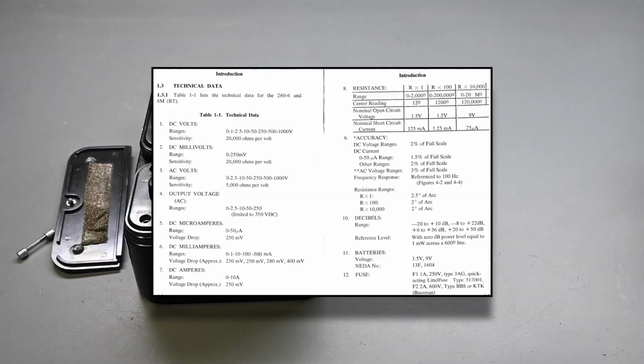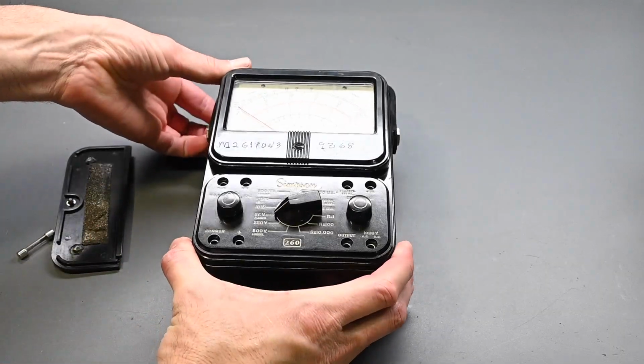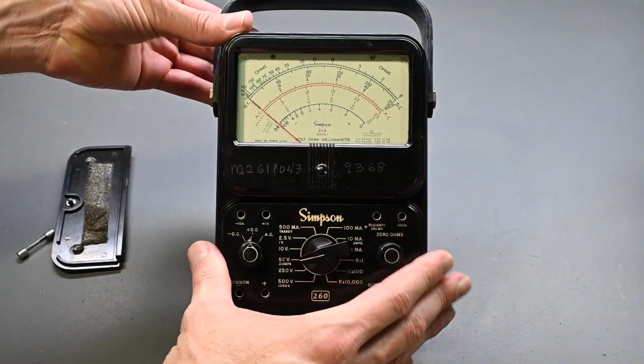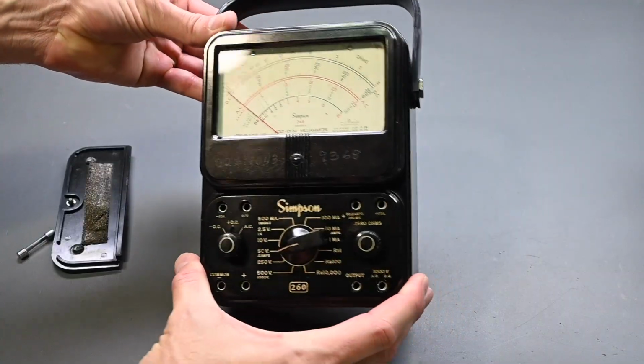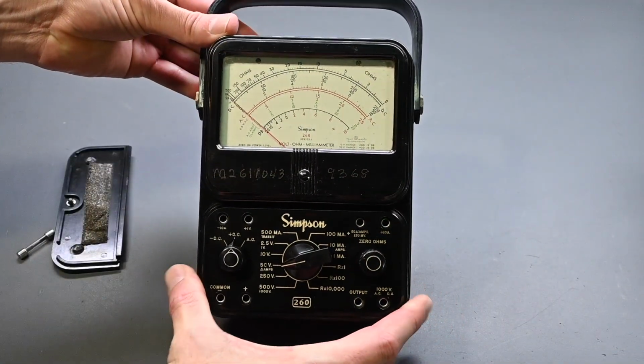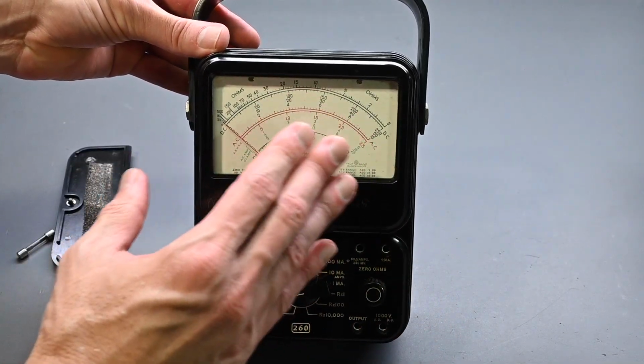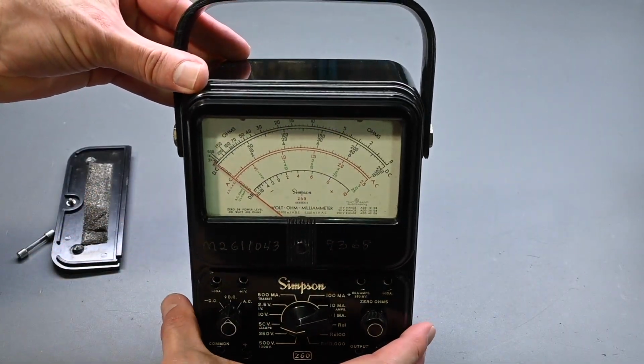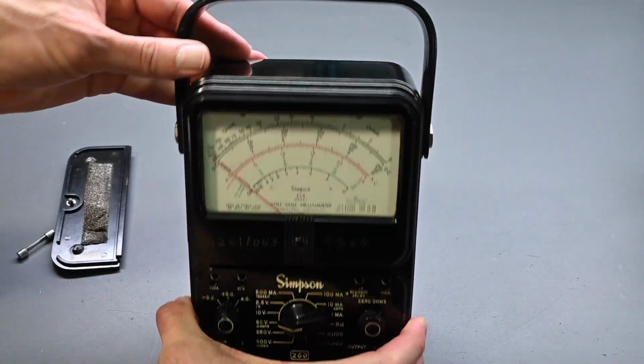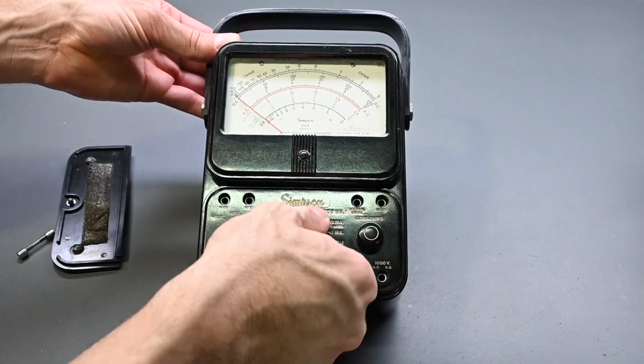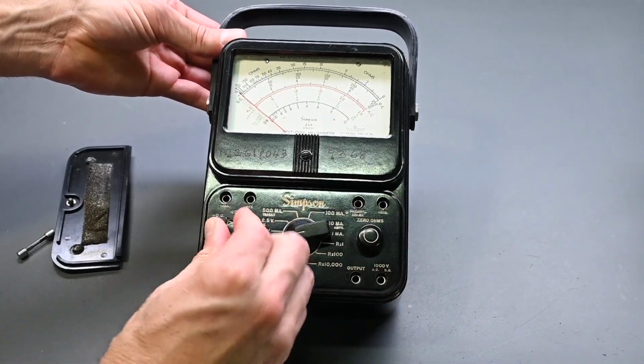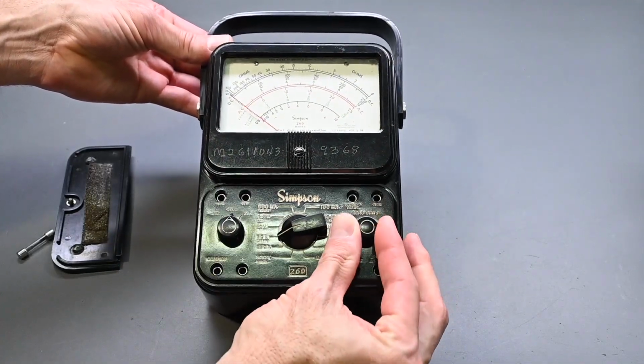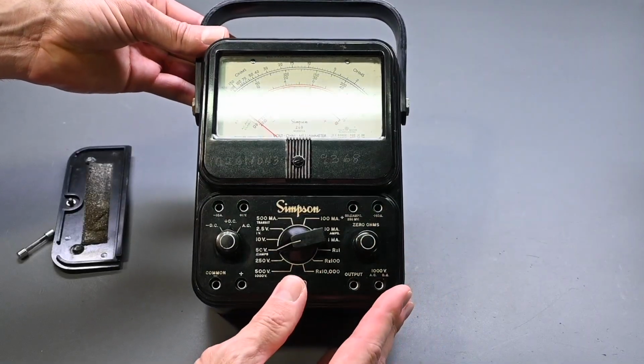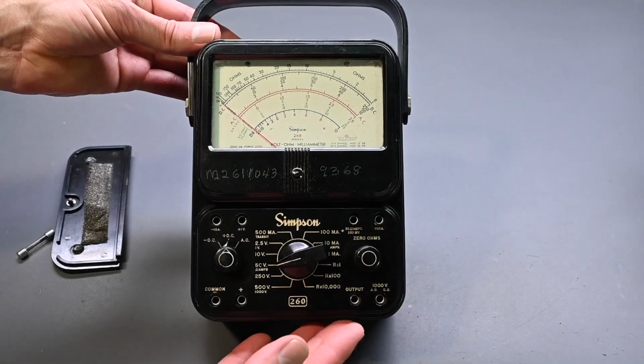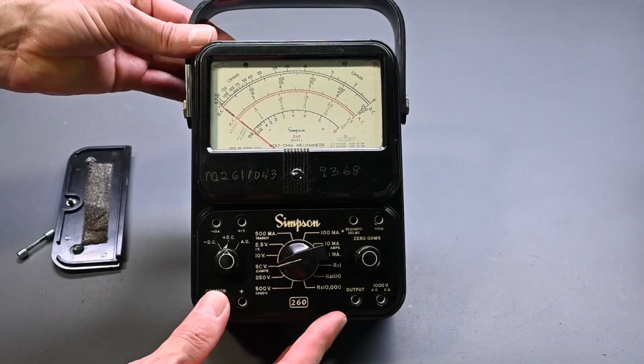Let's take a look at the meter. It looks to be in nice cosmetic condition. I don't see any damage to the case, no scratches or cracks. The glass is in good condition, and the face of the meter, the dial, is in very nice condition as well. The handle's in good shape, the switches rotate smoothly, nothing's binding up, and the zero ohms potentiometer turns very easily. So for the age of the instrument, it looks to be in nice external condition.